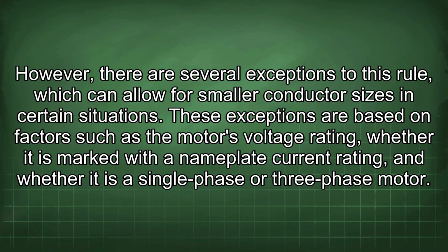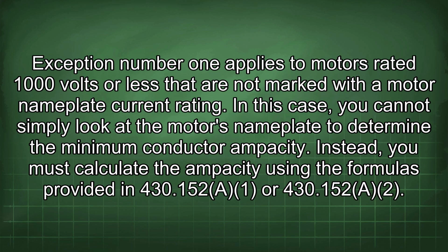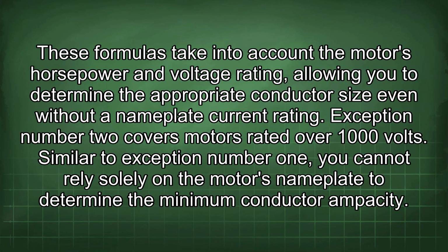These exceptions are based on factors such as the motor's voltage rating, whether it is marked with a nameplate current rating, and whether it is a single-phase or three-phase motor. Exception number 1 applies to motors rated 1000 volts or less that are not marked with a motor nameplate current rating. In this case, you cannot simply look at the motor's nameplate to determine the minimum conductor ampacity. Instead, you must calculate the ampacity using the formulas provided in 430.152. These formulas take into account the motor's horsepower and voltage rating, allowing you to determine the appropriate conductor size even without a nameplate current rating.